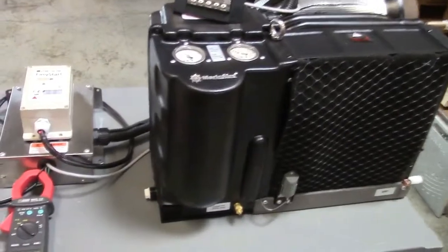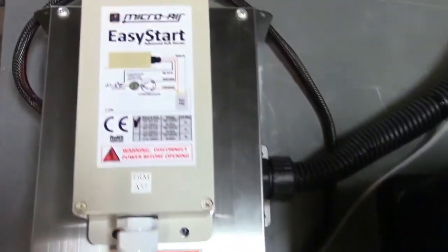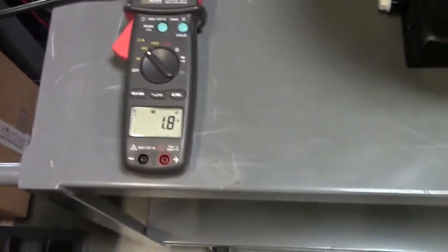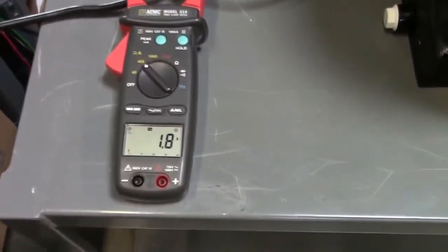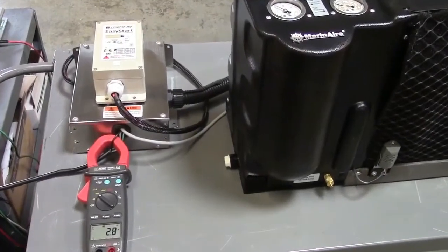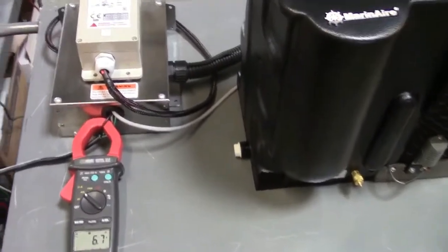Now let's see how easy this MarinAire unit 16,000 BTU starts with the Micro Air Easy Start installed. We've got our peak recording ammeter here. There's a delay built into the Easy Start at 15 seconds, so it's going to take a while.